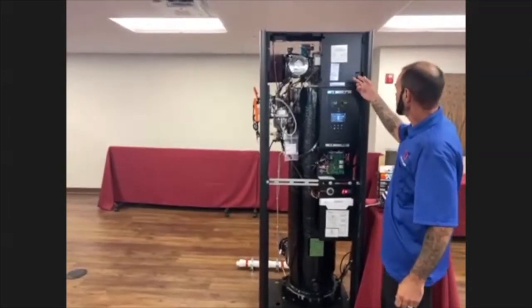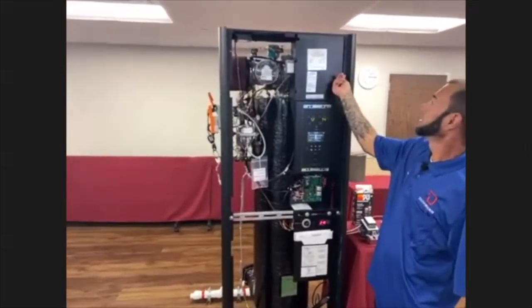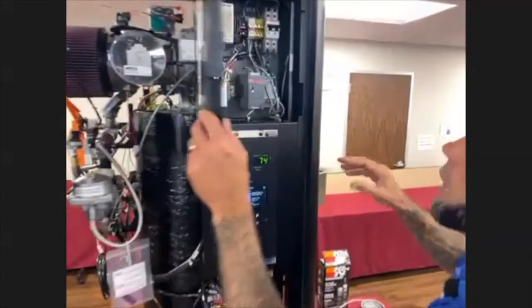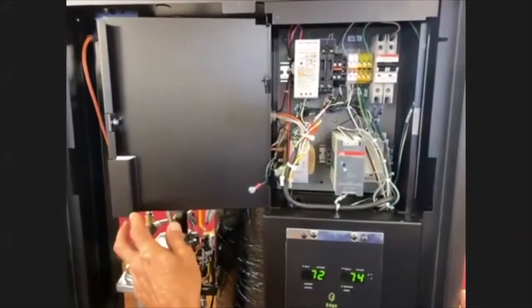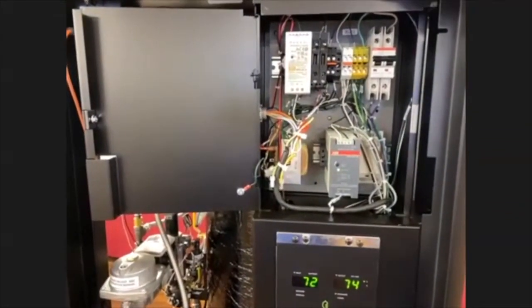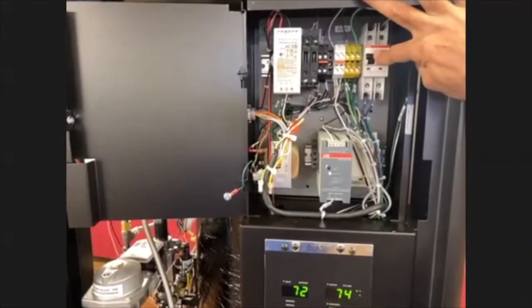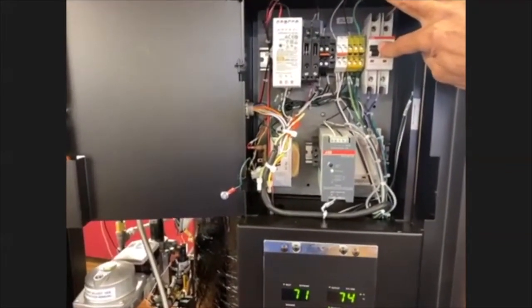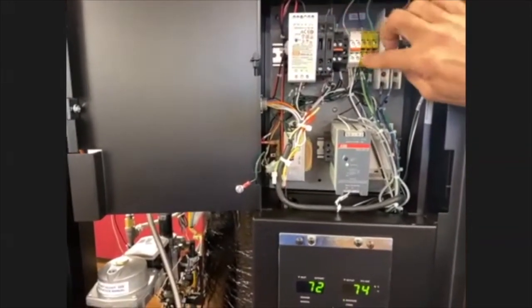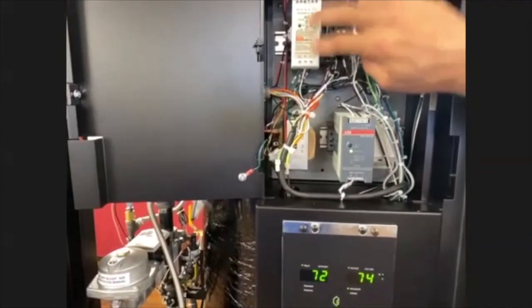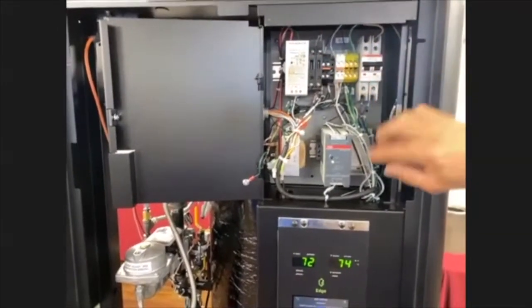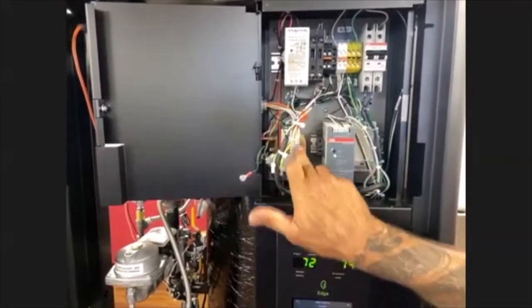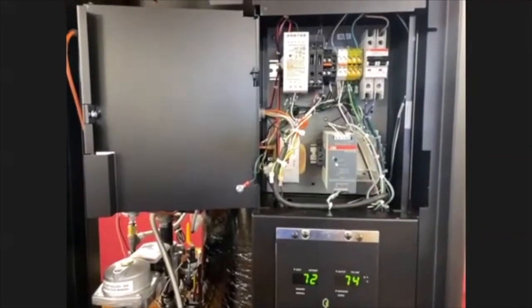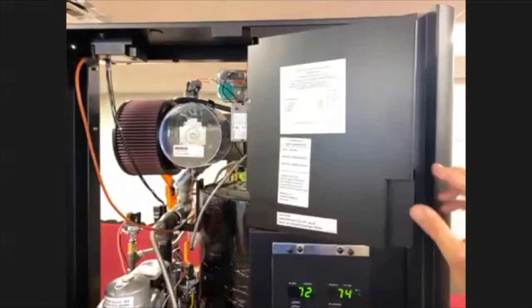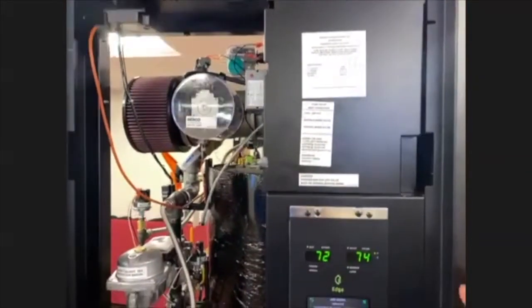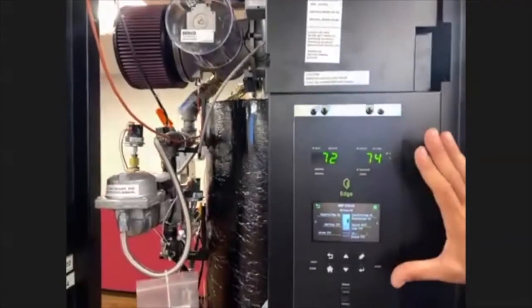So the first thing we'll look at here is our power supply. We open up this cover here. Our power comes in from the top into the breaker supplied by the manufacturer. We have our connections for neutral, ground, our fuses, DC power supply, amplifier, and low voltage step-down transformer. From there, we step down into our display.